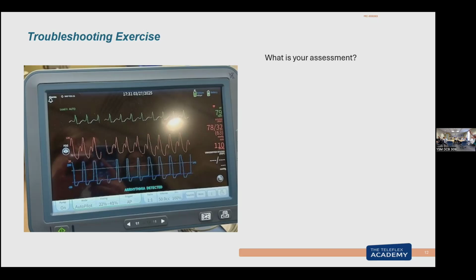Now, this is what I always found interesting, but don't go past, there's my hash marks on that. Don't go past the halfway mark. I thought, well, why not? You got hash marks below. I used to have one of those nurses. What happens if I go below? What happens is you're not driving that 60 to 70 as fast. I'm getting less volume, but I have no idea. The problem is you might not be getting enough balloon inflation and could have folds on the balloon. So that's control of augmentation.